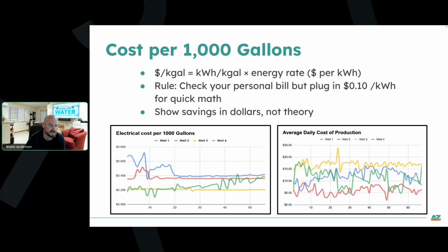Well three is just as steady as it goes, and then well four starts off relatively steady, kind of dips and rises. But then you can see it start trending up over time, and it's starting to increase and really get outside of what the norms are. And so where it ends versus where it started, it's running at about half the efficiency that it was.